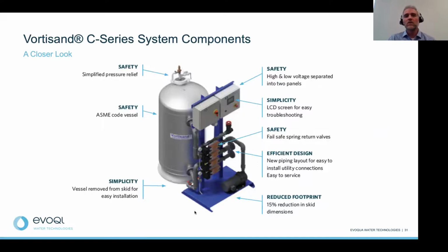Let's take a little bit closer look into the overall product. Really, this product, the Vortisand C series system, was recently released as an improvement directed specifically to customers in a cooling environment, both open and closed loop systems. It's again this technology, fully automatic, plug and play, fully controllable with a PLC. We've really focused on safety, from pressure relief valves to utilizing ASME code vessels to even separating high and low voltage panels, so ultimately reducing safety concerns from when your staff is out on site.